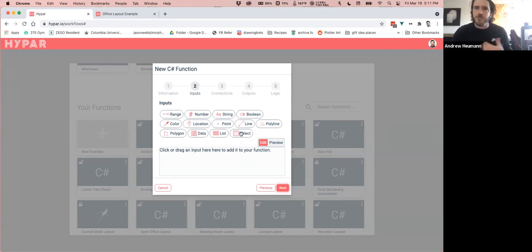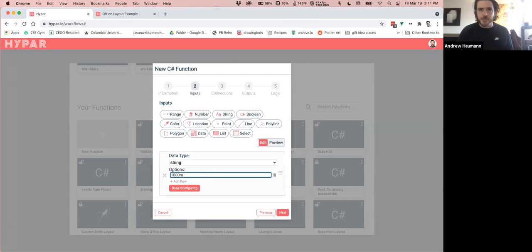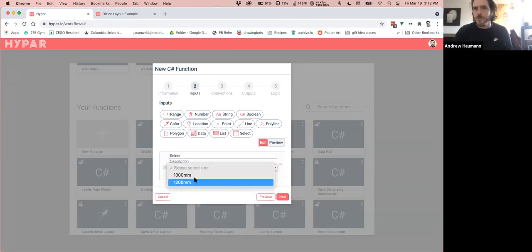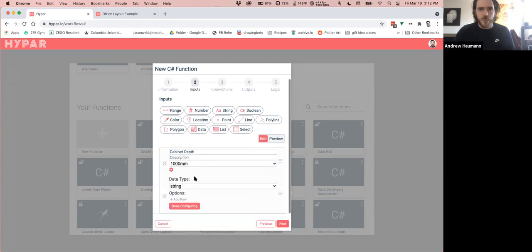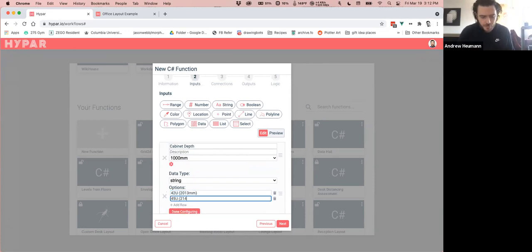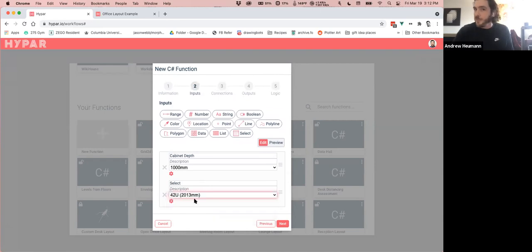I'll set up a handful of inputs to drive the logic. There are a few different data racks to choose from, starting with a Revit family that has a few options: a 1,000mm depth option and a 1,200mm depth option — so I'm setting up options for a cabinet depth dropdown. Then I'll do the same for cabinet height with preset options: 42U (about 2,013mm), 45U (2,146mm), and 48U (2,280mm).